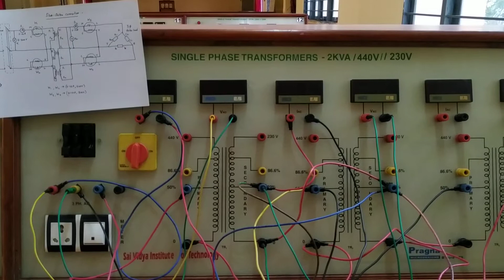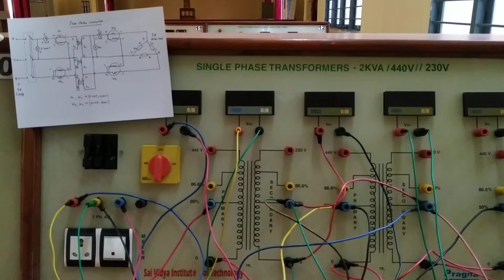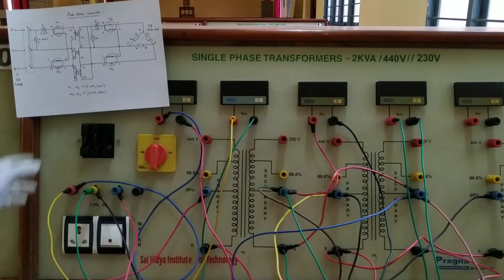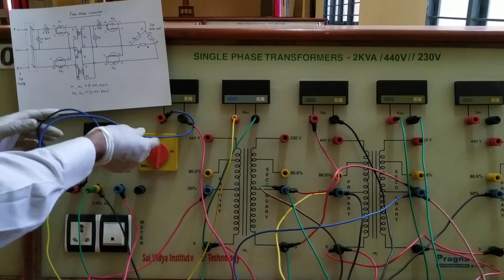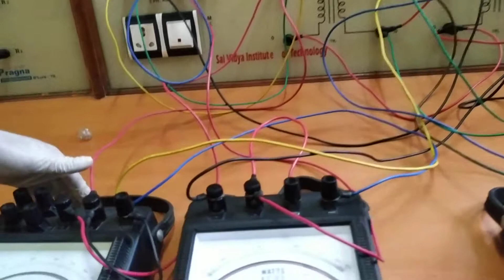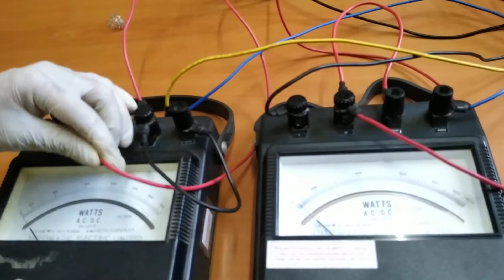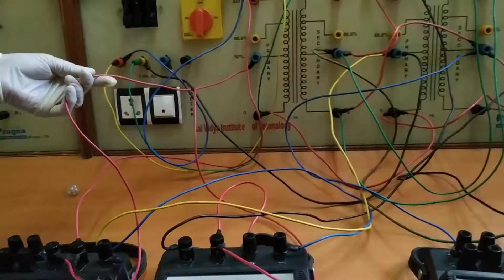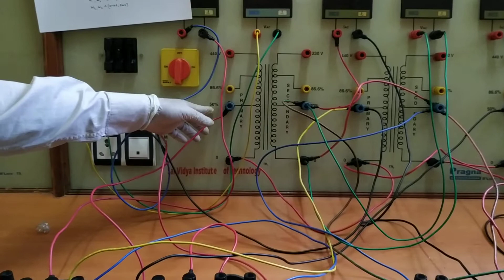This is the setup we have for load test on three single phase transformers. So let us see the circuit configuration, circuit connectivity one by one. So we start with supply R. From R it is connected to an ammeter. So we have R, Y and B over here. From R it goes to ammeter. From the other end of the ammeter it is connected to M terminal of the wattmeter. It is connected to M of wattmeter, and from the L line of the wattmeter it is connected to P1 of the first transformer, which is at 50% tapping, as you can see it clearly.